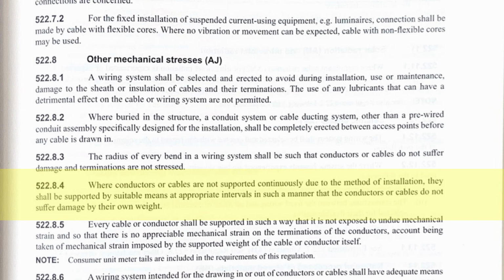How much of a mess would things be in if we didn't have all these pieces of information to design circuits? Well, you only have to look in the past, hey? We can also protect cables by making sure that they're supported, following regulation 522.8.4 of BS 7671. The regs also consider cable bends.